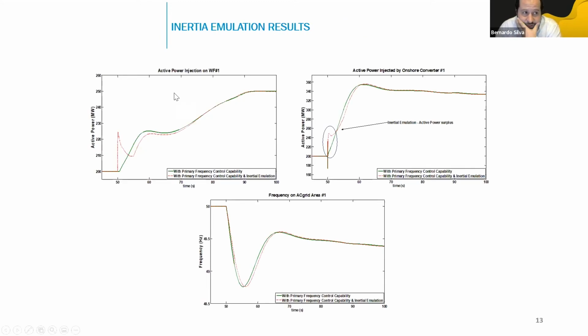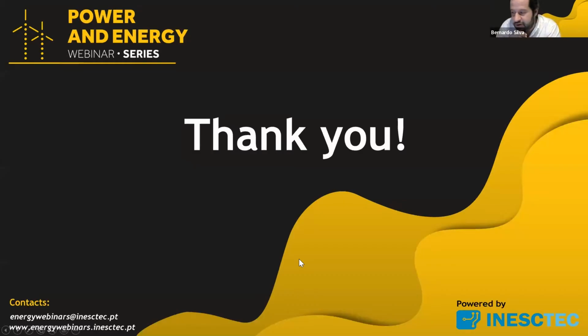With these results, by adding this frequency inertia emulation capability to the primary frequency control, we can see the turbine is able to quickly increase power, which is then reduced due to the loss of kinetic energy. This is normal behavior. More importantly, this power was channeled towards the affected area, proving effective even for these disturbances. The impact on frequency can be measured by the rate of change of frequency, which is reduced from one case to the other. With this, I finish my presentation on primary frequency control.